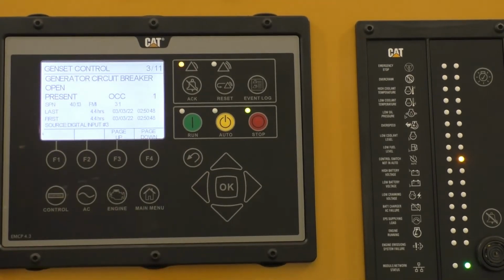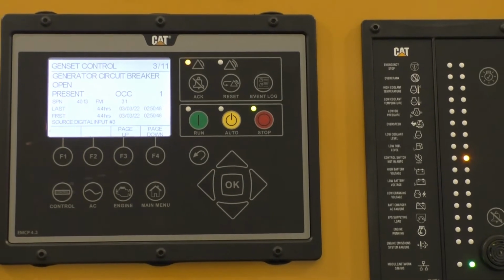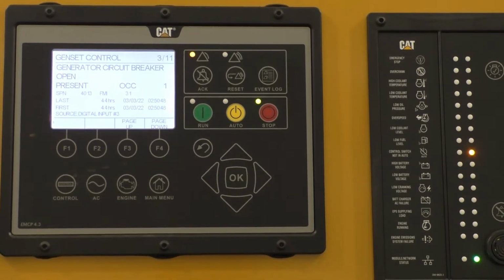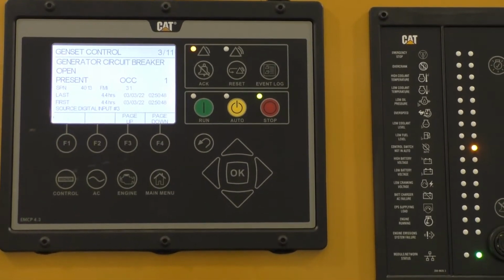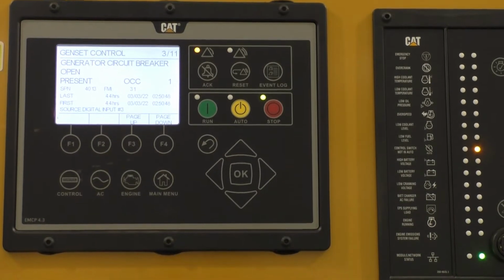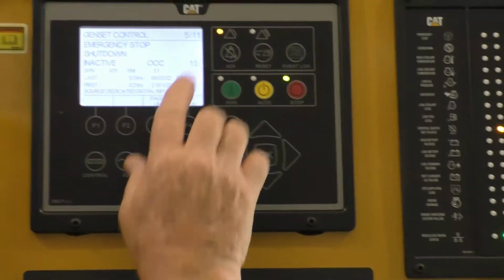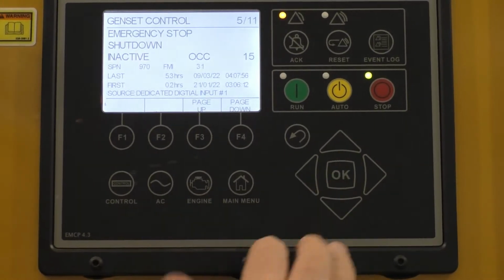Generator circuit breaker open present. That's this one that feeds the 2 transfer switches in the electrical room. They're open because I wasn't asked to leave them in auto yet. Whenever that happens, we just close the breaker and so on, and that alarm will go away. But you can look at the list of alarms. It'll tell you first and last occurrence, the hours and the date that it happened, and all those things.